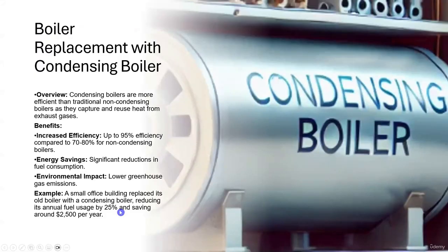Boiler replacement with condensing boiler. Condensing boilers are more efficient than traditional non-condensing boilers as they capture and reuse heat from exhaust gas. Increased efficiency, up to 95% efficiency compared to 70 to 80% for non-condensing boilers. Energy savings, significant reductions in fuel consumption. Environmental impact, lower greenhouse gas emissions. Example, a small office building replaces its old boiler with a condensing boiler, reducing its annual fuel usage by 25% and saving around $2,500 per year.